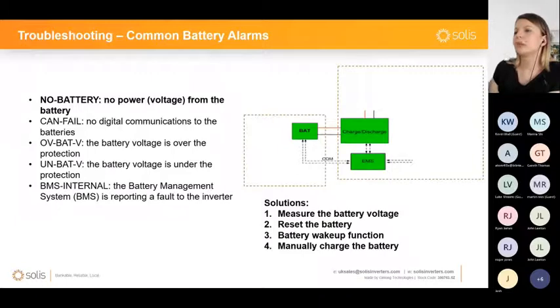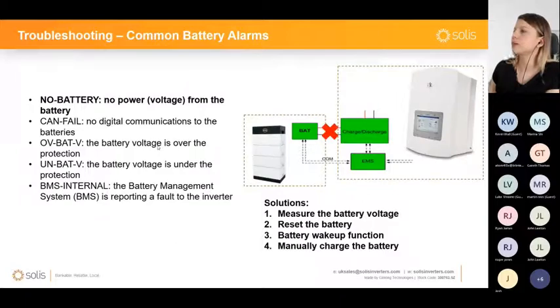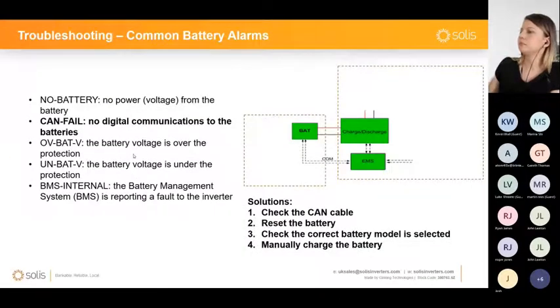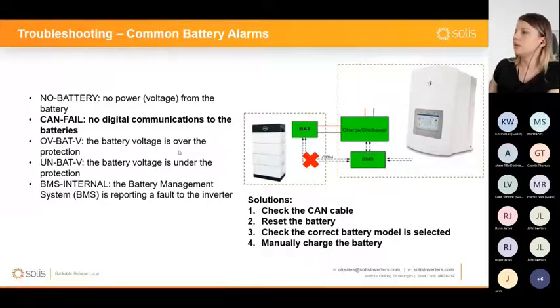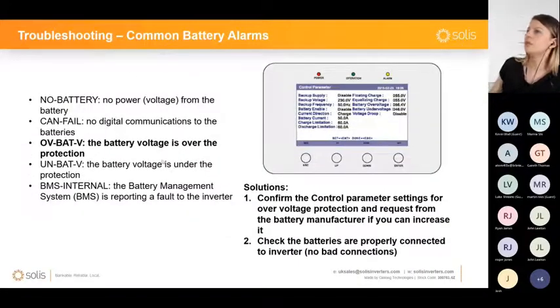An under voltage battery alarm, that's almost always an indicator that the battery is depleted, it's completely empty. And you can also check this by measuring the voltage on the battery information in the information menu of the inverter. I think, yeah, I have gone through these over voltage.